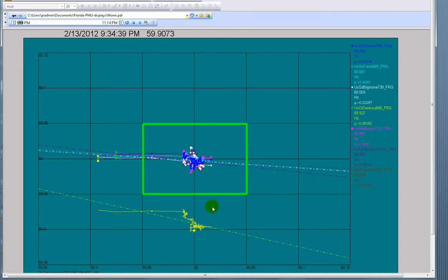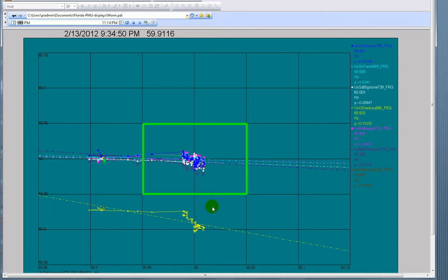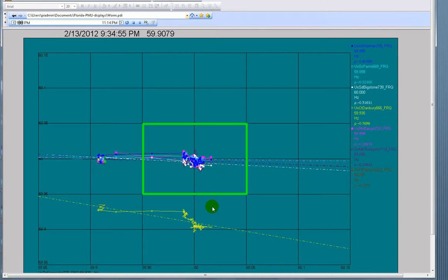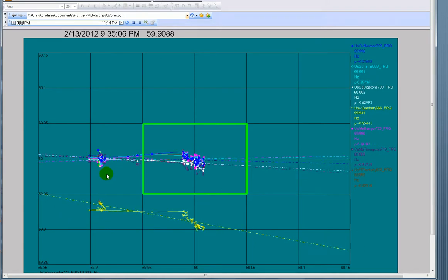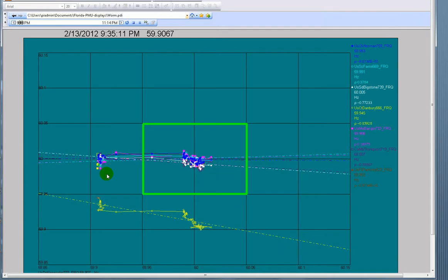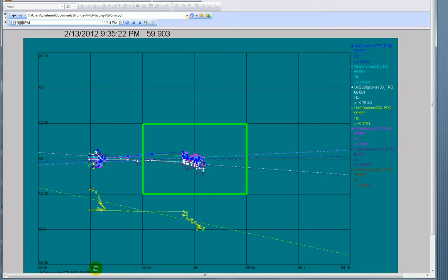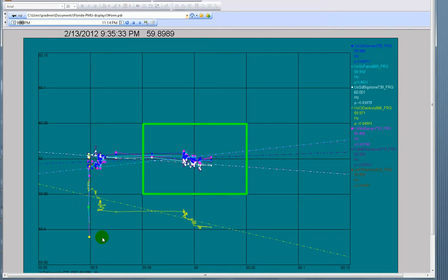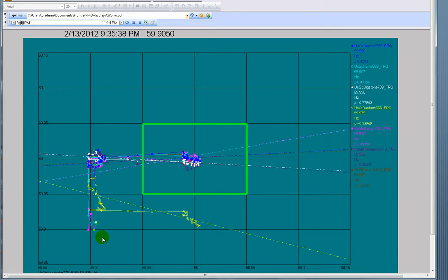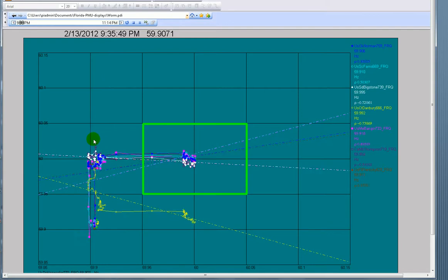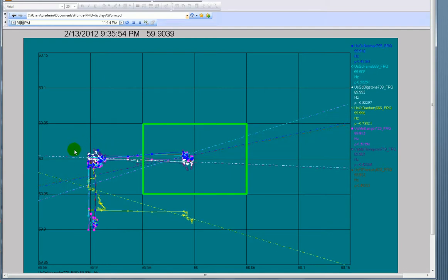Now you'll see the case where Danbury has lost load in its area and the frequency has dropped down to 59.9. Most of the other stations in the grid have also dropped down to 59.9 with respect to Knoxville. So this is again saying that the system is operating as two separate asynchronous machines. However, the Danbury trace, you can see, is trying to get into this cluster operating at 59.9.